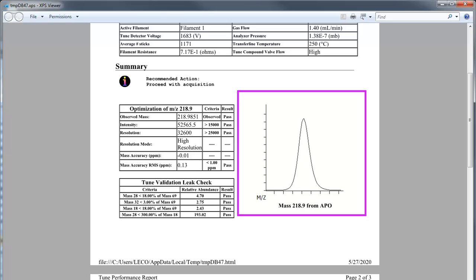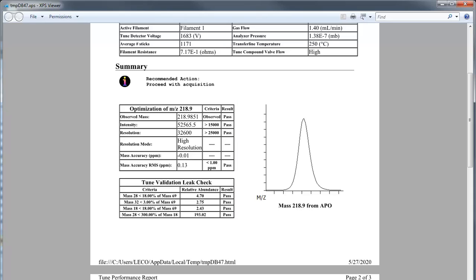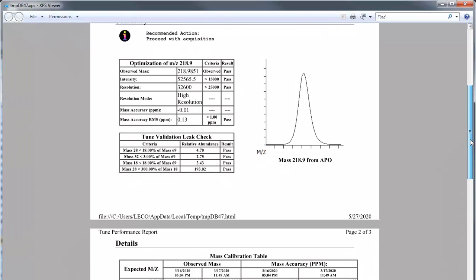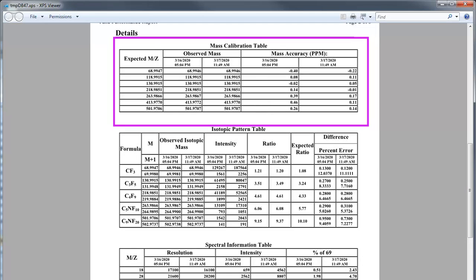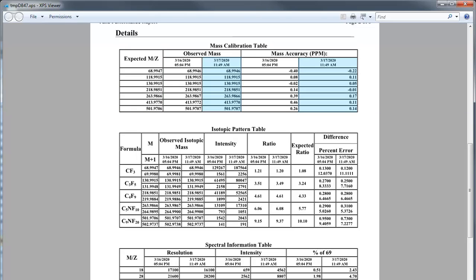The profile plot of mass to charge 219 gathered from the latest APO performed on this mass spec method is displayed so that the user may visually check for excessive tailing, asymmetry, or skew which may have occurred during optimization. The calibration table is a portion of the calibration matrix which shows the expected masses and mass accuracy from the PFTBA analyzed during tune validation. It also shows the results from the last tune validation run prior to this analysis for comparison.